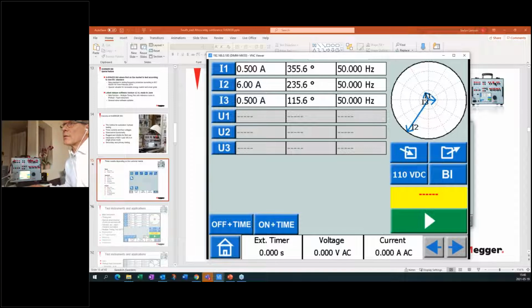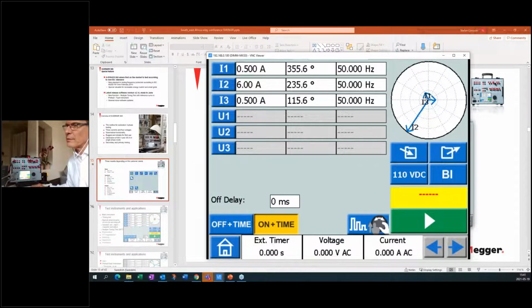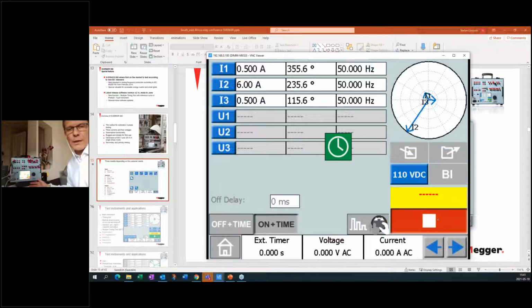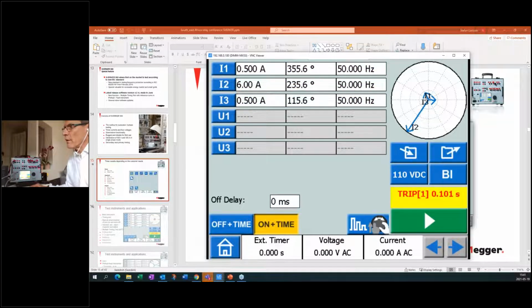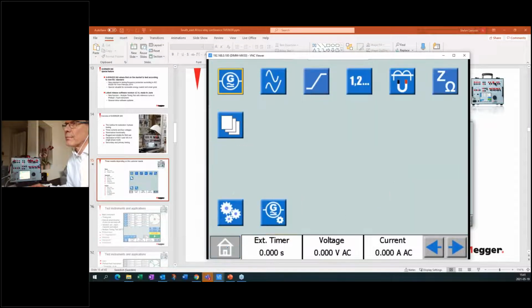And in this case, we can see it's set to 0.5 on phase 1, phase 2 is 6 amp, and phase 3 is 0.5. So I know the protection has the highest threshold at 5 amp, and if we are over 5 amp, we will have around 100 milliseconds. And the time is in the yellow field here. Then I just go and do the test. But first I need to do the on plus time to tell that I would like to measure the time. I click the play button. And then we have the result. It's 101 milliseconds. So this was a timing test done on an overcurrent protection.